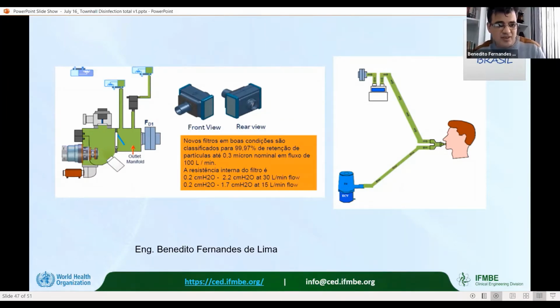In this case, only ventilation equipment with double circuits is permitted, because it's possible to install HEPA filters at the end of the exhaling tube. However, most filters are capable of filtering up to 0.3 microns, and no manufacturer guarantees that the filters will retain coronavirus. Manufacturers also report there are several factors that can trap the contaminants in the filter. Many ventilation equipments now started to be used only with coronavirus patients.